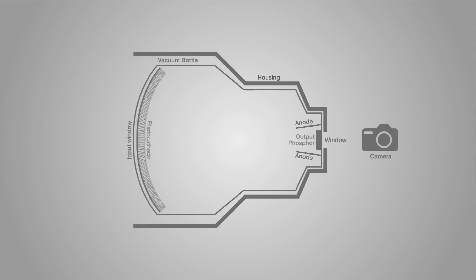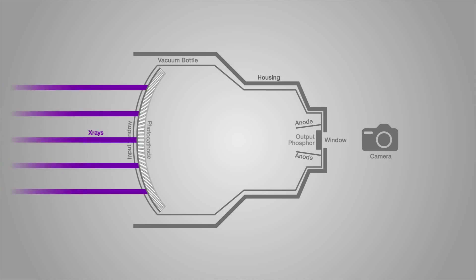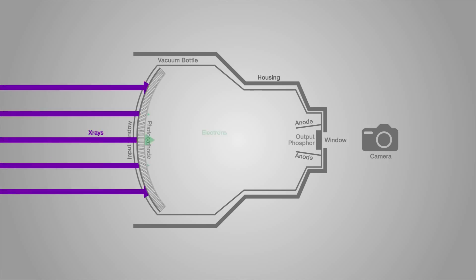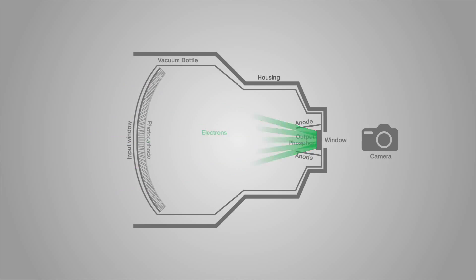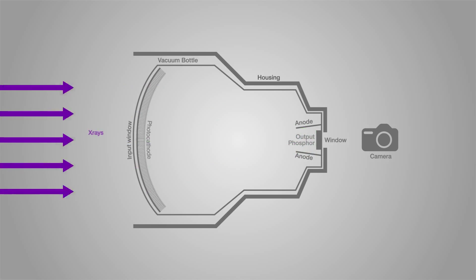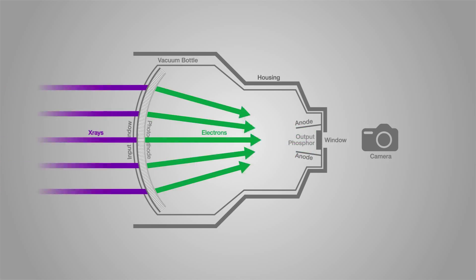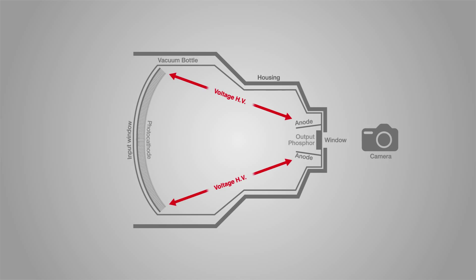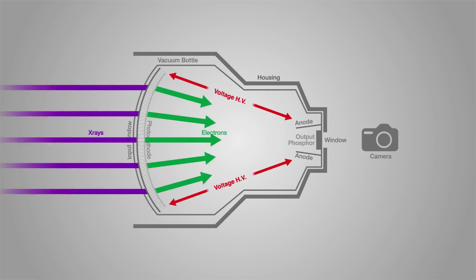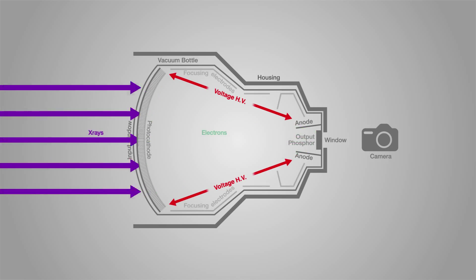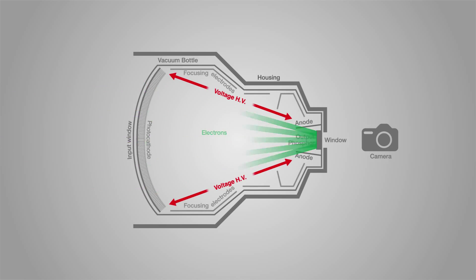This animation demonstrates the principles by which all X-ray image intensifiers operate. The X-rays arrive at the input window, where they are converted to a stream of electrons, which can be accelerated towards the anode by a high voltage and focused by electrodes positioned along the path.